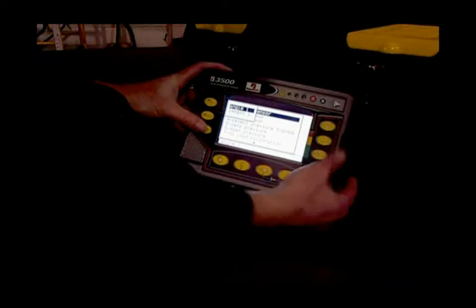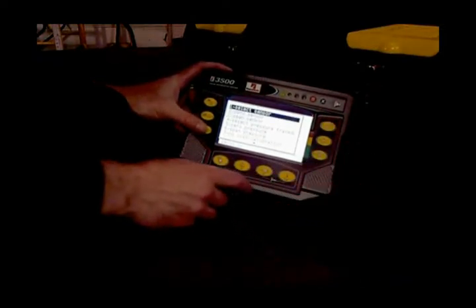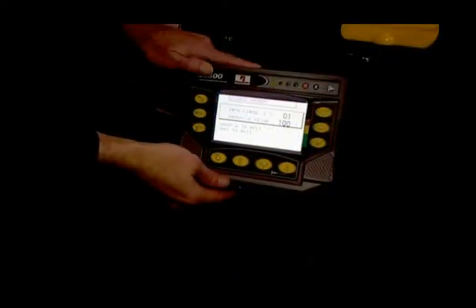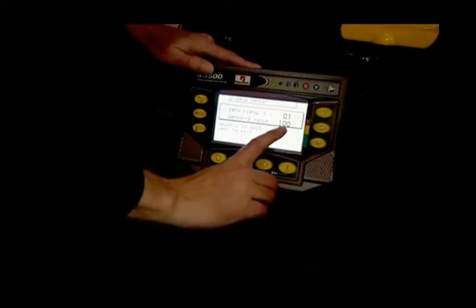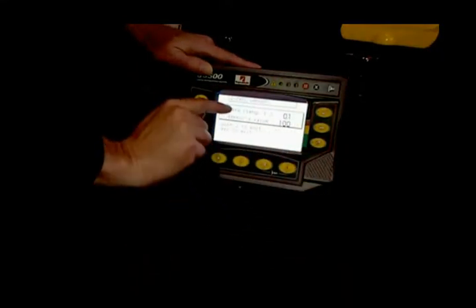And we're going to make sure that we have the correct sensor selected. So it's already sitting on select sensor. We're going to hit the check mark, drop it down to length 1, hit the check mark again, and now we're going to drop it down to zero the sensor. So after we're in here to zero the sensor, what you're going to see is you've got a 100 for your digital value, and you've got a 0.1 in this case, or 0.0 for your actual zeroing of your length.